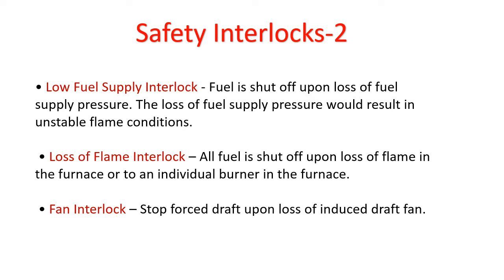Now, if the fuel supply pressure is low, then obviously you need to shut down your fuel valve because this will result in an unstable flame condition. Then there is loss of flame, which may be due to loss of fuel, loss of air, loss of ignition, or improper fuel-to-air ratio, or anything. Any time this situation happens, obviously you need to close the fuel gas valve so that your boiler can be saved. Another is the fan interlock.